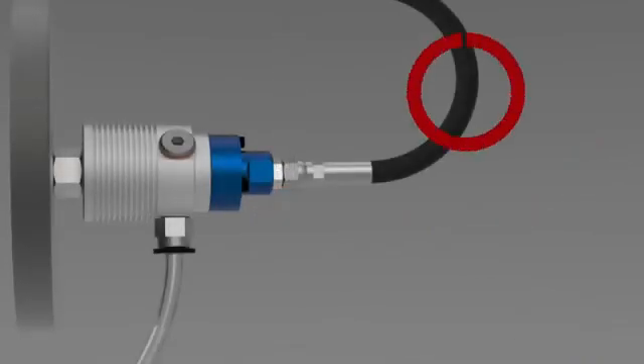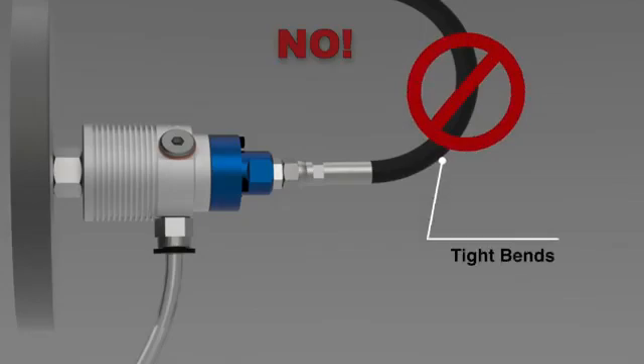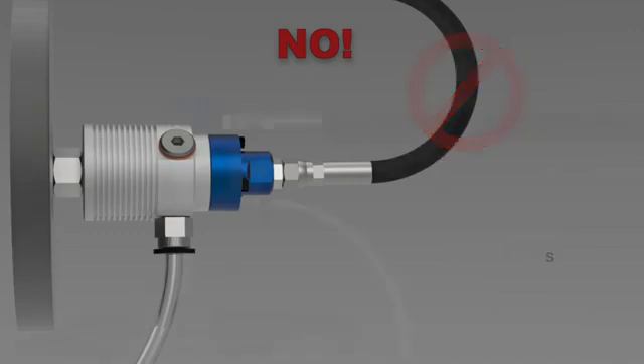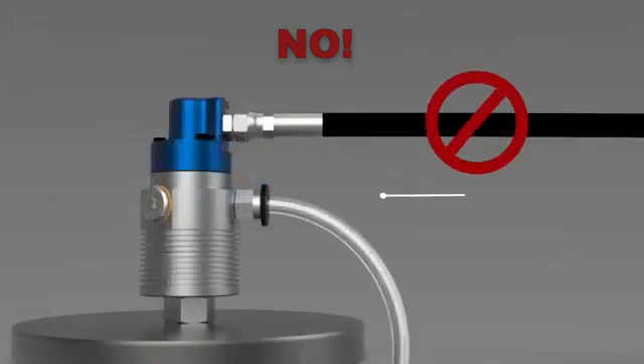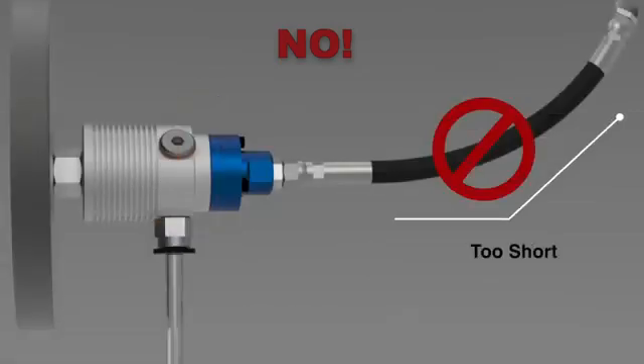Make sure that the union will not experience any side loads during operation. Excessive side loads can interfere with sealing and shorten bearing life. Such side loads can be caused by supply hoses with tight bends, hoses that are too tight, or hoses that are too short.